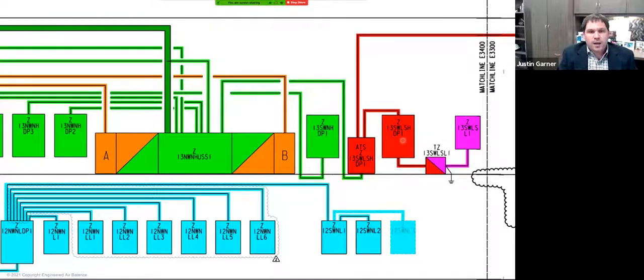So that's how the emergency power and utility power tie together in a very simple sense. It's interesting to note that most large HVAC equipment in buildings is fed typically out of distribution panels. So you're normally going to have a piece of switchgear. It's going to have larger breakers. Normally these are in the 400 to 2000 amp range. In a central utility plant, you might feed a large piece of equipment like a chiller directly off of a breaker in a piece of switchgear. But normally it's going to be distributed down to a distribution panel.